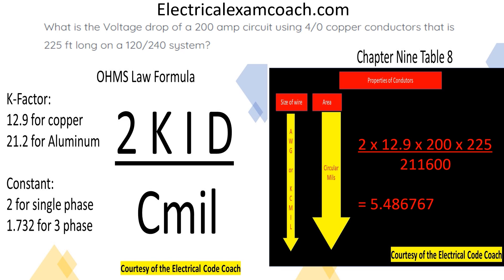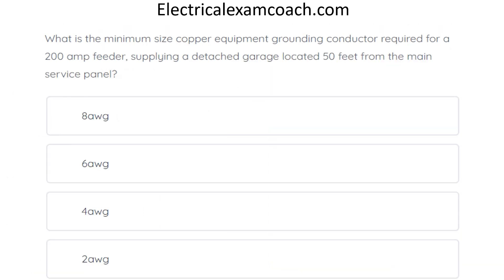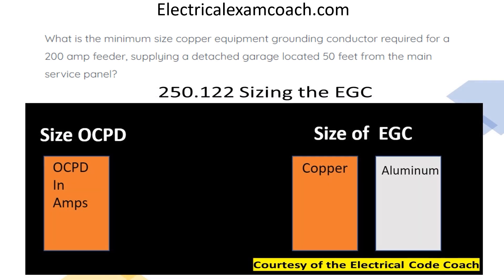What is the minimum-sized copper equipment grounding conductor required for a 200-amp feeder supplying a detached garage located 50 feet from the main service panel? The correct answer is 6-gauge wire. The distance from the panel doesn't matter — test makers love to include details like that to throw you off. The EGC size is determined by Table 250.122. We start on the left-hand side, select our overcurrent protective device size of 200 amps, cross over to the copper column, and select number 6.